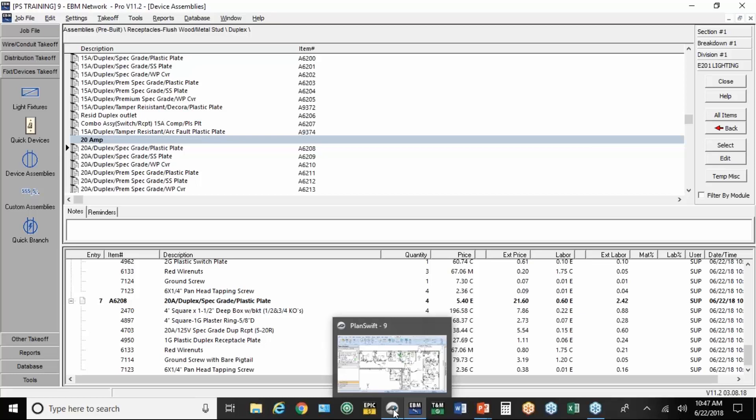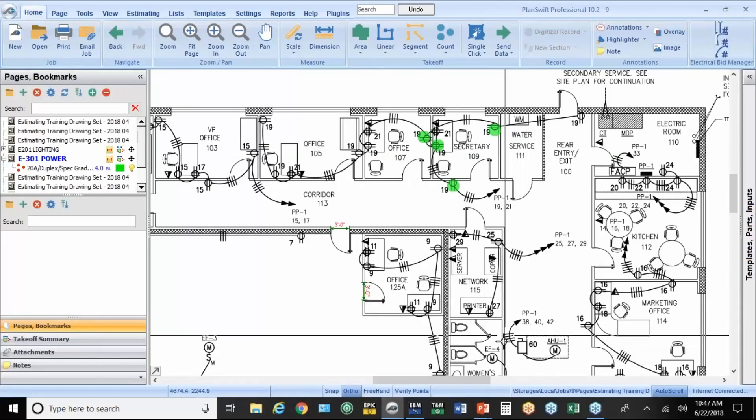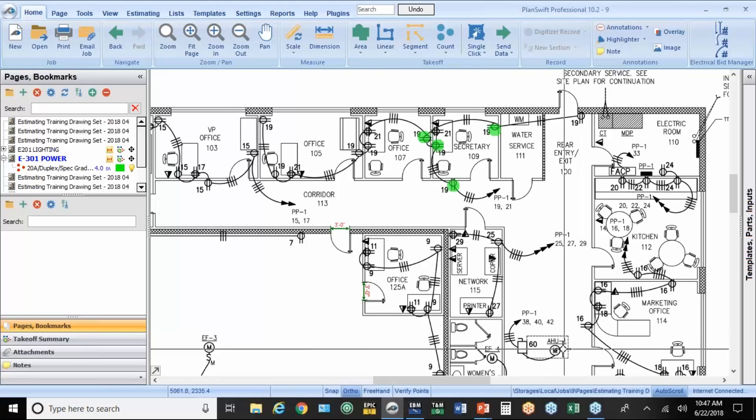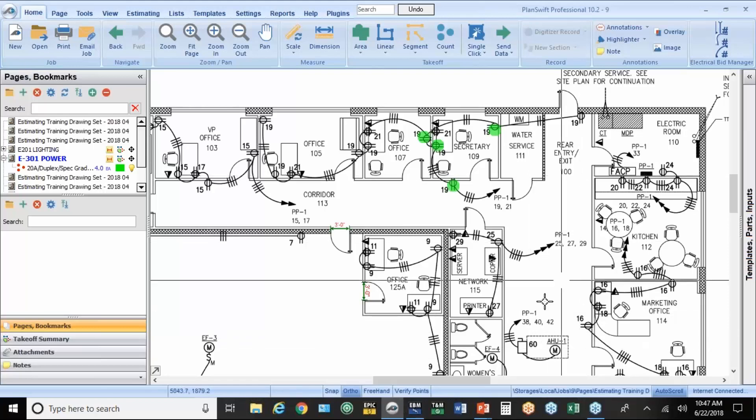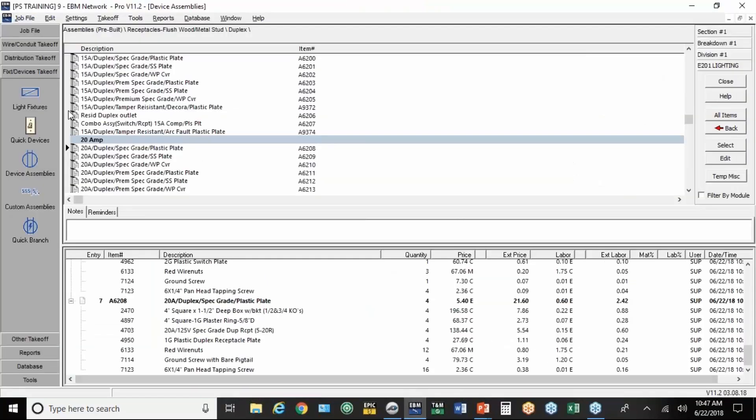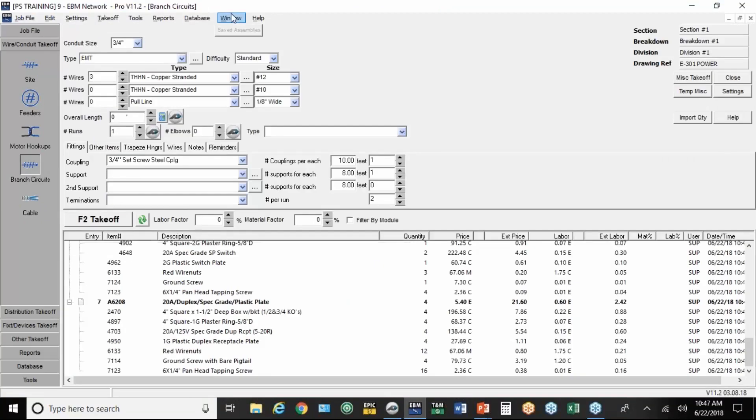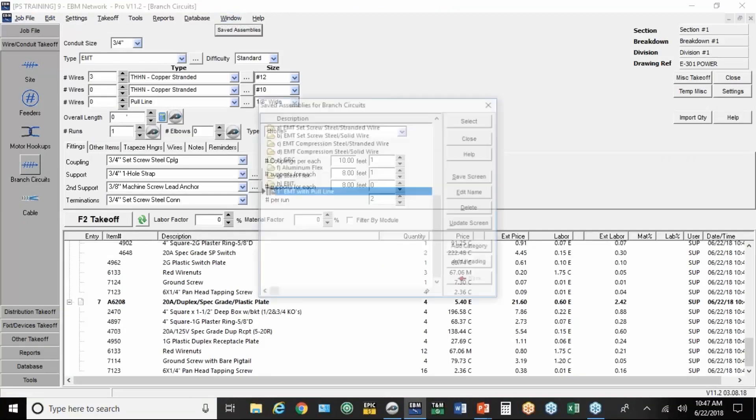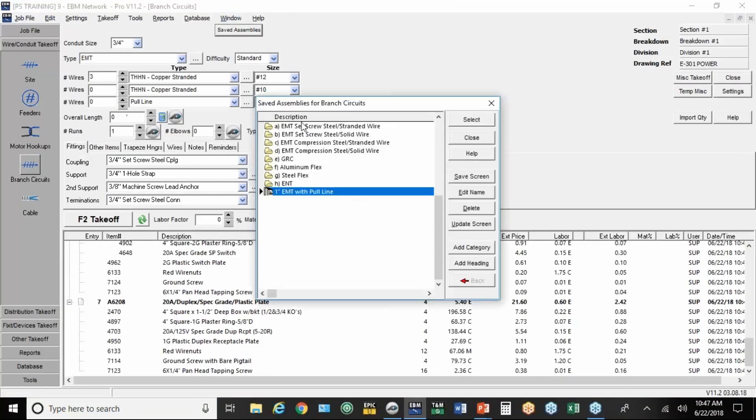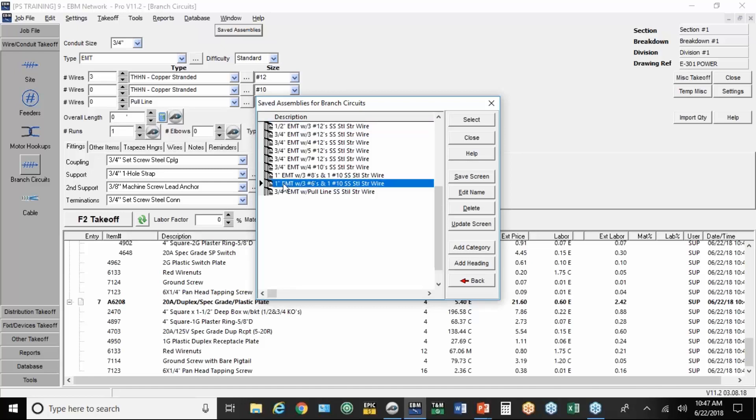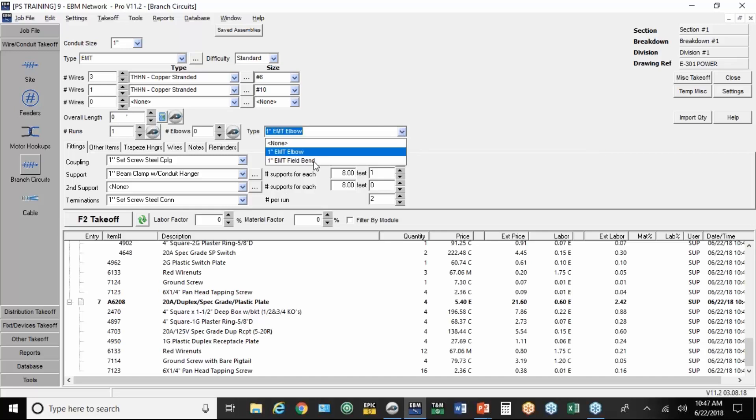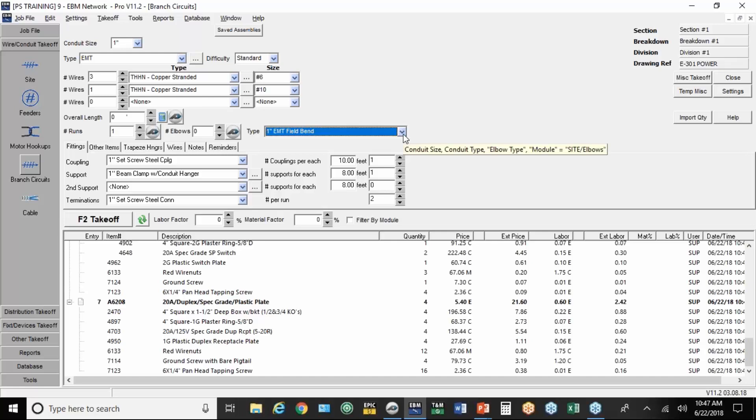Now to measure, you can see this 60 amp disconnect here on the air handler unit. It goes up to panel PP2 in the top right. So I need to measure up and over. You do that by going to EBM, just to where you normally would under branch circuits. We're going to go to saved assemblies. Set screw steel stranded wire. One inch with three sixes and a ten. Now we can count elbows, and they can be field bends or factory elbows. I'll do a field bend.